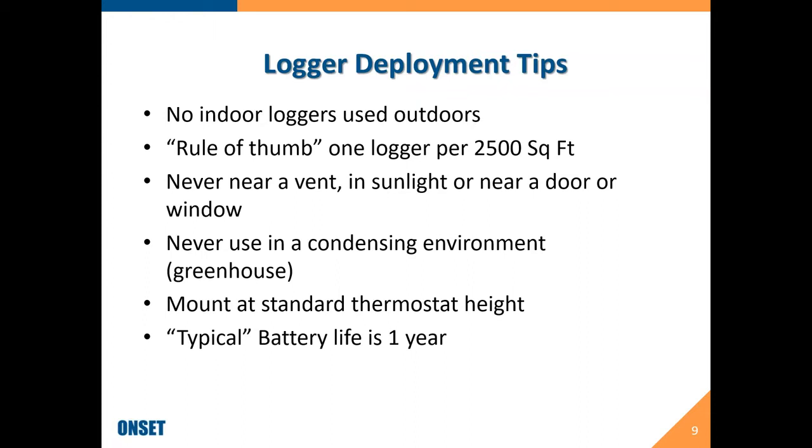Use 2,500 square feet as a rule of thumb. When you deploy a logger, you never want to deploy it near a vent where it would be blown on with cooling or heating air. You don't want to put it in a place where the sun hits it. Otherwise, you'll get defective readings because of the heating of the sun, or near a door or window. If somebody opens a window and you're trying to get a temperature and relative humidity profile, they'll throw everything off by doing that. Never use indoor loggers in a condensing environment. A condensing environment would be like a greenhouse. A lot of people think that even though a greenhouse is indoors, it is really an outdoor environment.